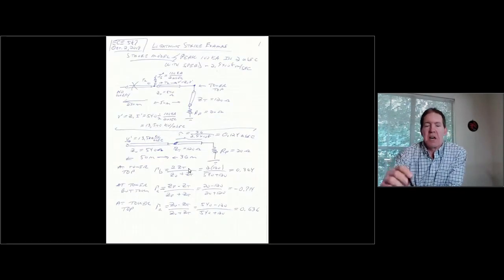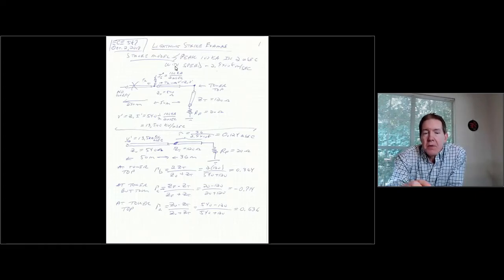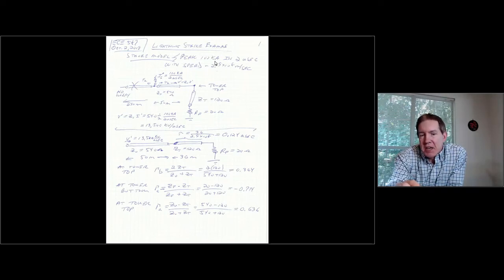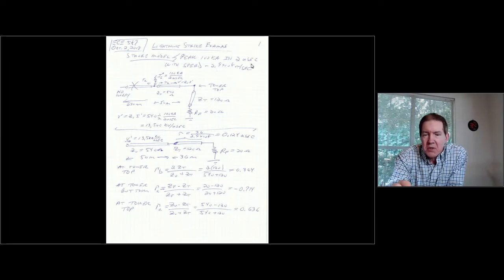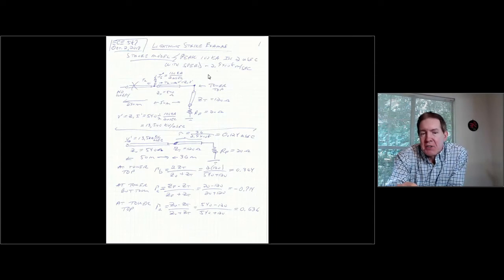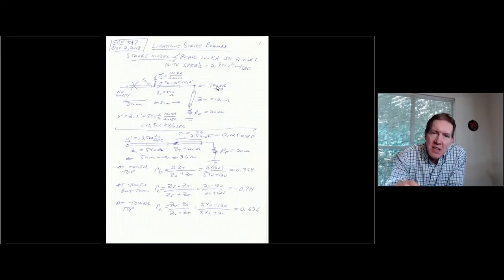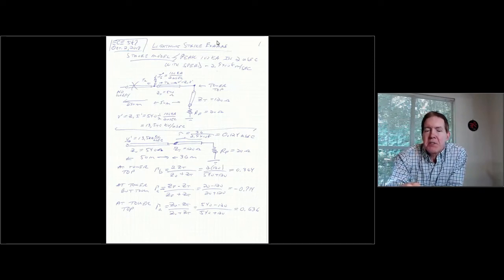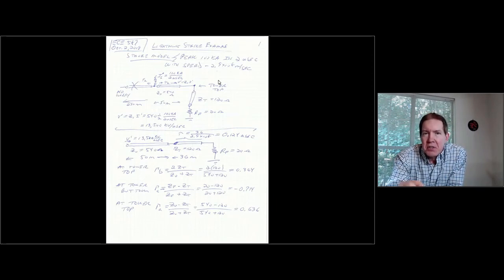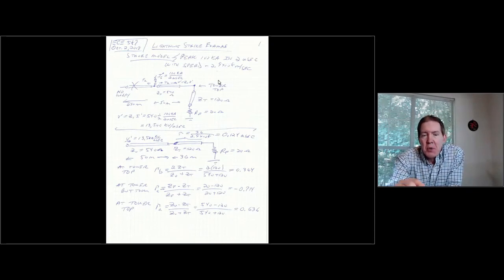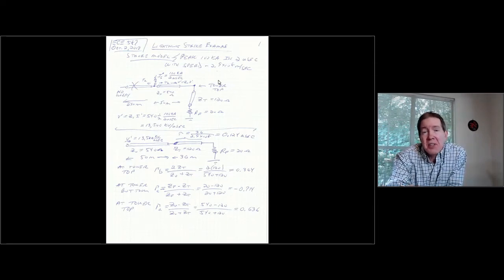When we work this out with the hand analysis, the stroke model has 100 kiloamps reached in 2 microseconds. The way we're going to model this is using the change in current with respect to time — the dI/dt. In the past we assumed a fixed voltage, but here we need to model the dI/dt, multiply by impedance and time to get the instantaneous voltage. Because if we have a triangular waveform, the voltage increases with time, and the effect we're looking at actually occurs before we hit that 100 kiloamp peak.